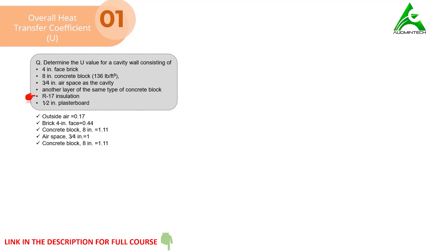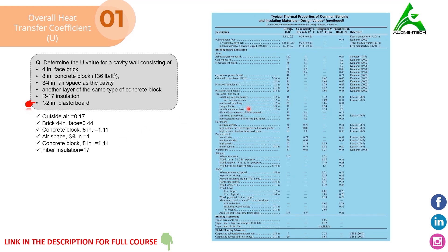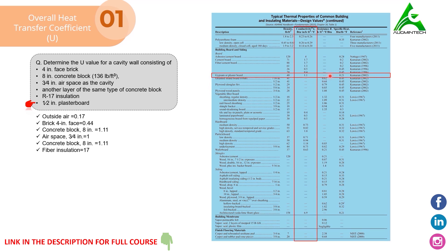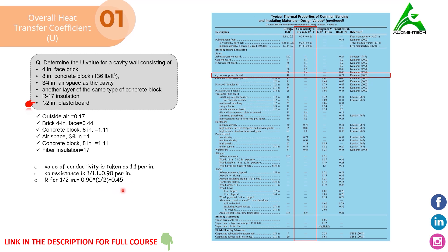Then we find the resistance of R-17 insulation. Because R-17 is mentioned, it simply means the resistance can be taken as 17. For the half-inch plasterboard, we use the same chart, selecting the row for gypsum or plasterboard and the column for conductivity since resistance is not directly mentioned. We get the conductivity value of 1.1, making the resistance 0.9 per inch for 1 inch. For half-inch, it is simply half of that, giving us a resistance of 0.45 for the half-inch plasterboard.